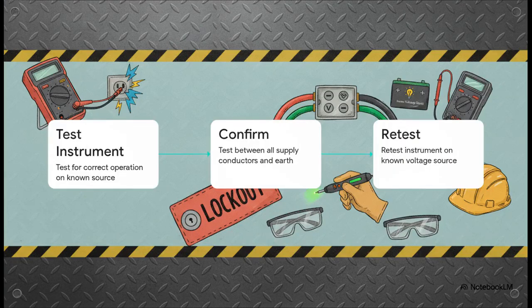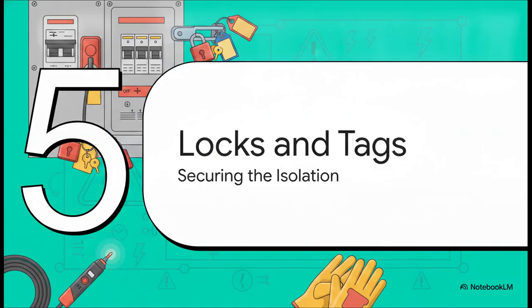Now, to make absolutely sure your test instrument isn't giving you a false negative, say you've got a blown internal fuse or the battery just died, you have to follow the 3-part testing rule. It's non-negotiable. Step 1. Test your instrument on a known voltage source to make sure it actually works. Step 2. Test between all supply conductors and between those conductors and a known earth to confirm the circuit is totally de-energized. Step 3. Retest your instrument on that known voltage source. If your meter doesn't read the known source on Step 3, your zero reading in Step 2 means absolutely nothing. Never trust your life to an untested meter.